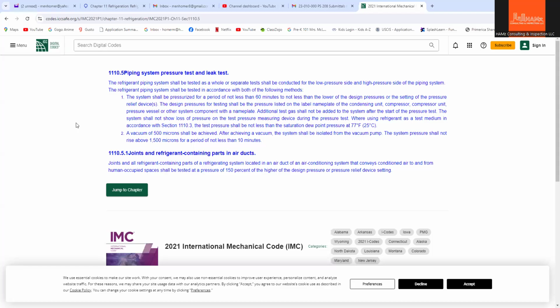So after testing, I have found some requirements that I could share under the refrigerant piping test. This is one of the requirements: the system shall be pressurized for a period not less than 60 minutes. So it's an hour test, to not less than the lower of the design pressure. So it's a pressure test not lower than what was specified on the nameplate of the condensing unit. It was stated right here, and the test medium was also.